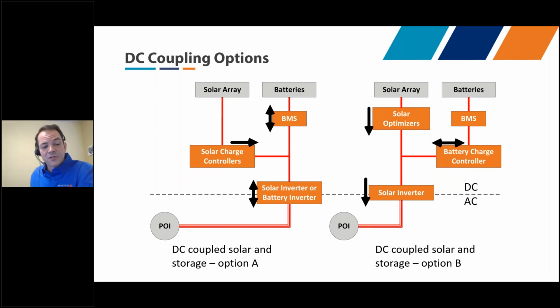We can compare that to the right-hand side, where there's a battery charge controller added in order to manage charging and discharging the batteries. This is a more common architecture when it's an existing solar system and you're adding storage to it. This may come up in applications like the recent Inflation Reduction Act, where you can go back and add storage to existing solar arrays, so these kinds of architectures often come out of that. You do need to be careful in applications like this to make sure the battery is not backfeeding into the solar array, so check that the solar equipment on site ensures that won't happen.